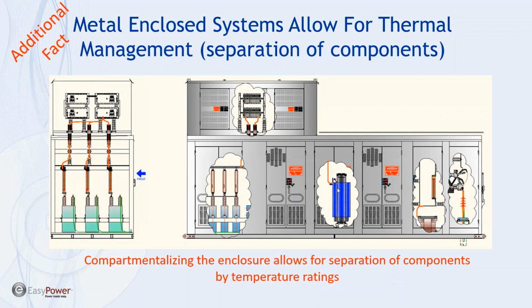For the reactor compartment, we also put a fan. There's higher losses in this compartment, but these losses equate to heat generated in this enclosure and temperature in this enclosure section. But this enclosure section is separated from the capacitor compartment. So I have a separation of devices, and therefore they all operate within their temperature rating. Another benefit of the metal-enclosed design: with an open air system, you're subjected to solar radiation, and you can't get around that.